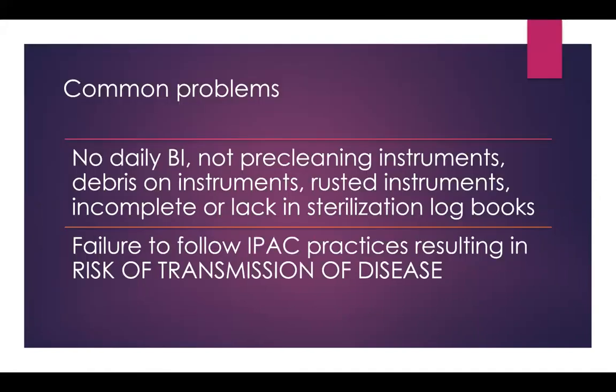Common problems that public health has found include: no daily biological indicators. Some offices were not doing it, or they claimed they were doing it but were not recording it — no logs. It's as simple as if you do not have a log of it, then it was never done. Also, not pre-cleaning instruments and debris on instruments.